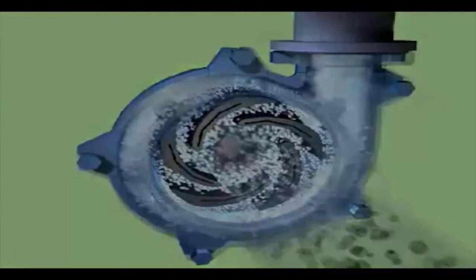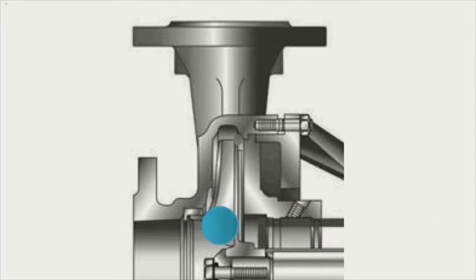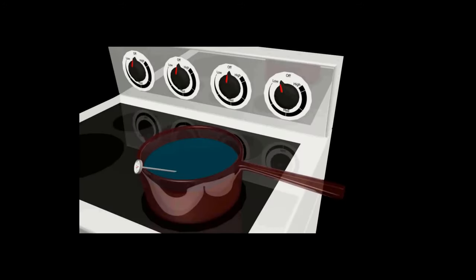Hello everyone, this is Karthik and welcome to the Pump Universe. Cavitation is the process of vapor bubble formation, then its journey towards implosion and microjet formation, leading to material erosion. Let's look at each phase in detail. Phase one is the formation of vapor bubbles — there are two possible reasons for a liquid to transform into a vapor.